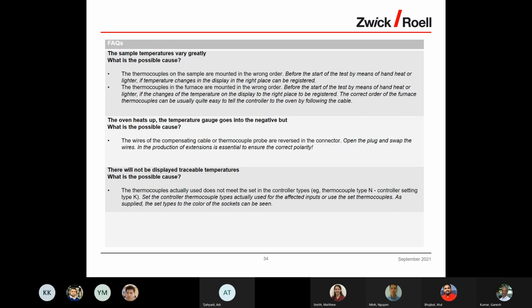The oven heats up, but the temperature gauge goes into the negative. What is the possible cause? The wires of the compensation cable or thermocouple probe are reversed in the connector. Open the plug and swap the wires. In the production of extensions, it is essential to ensure the correct polarity.